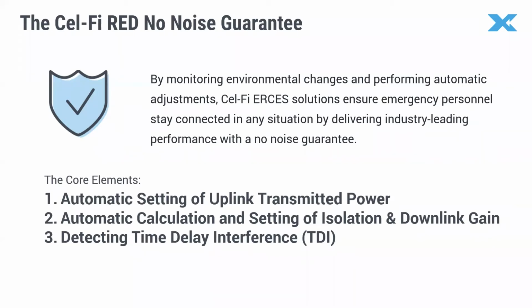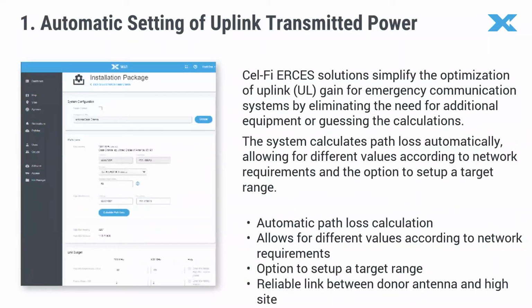Let's review the core elements, starting with the automatic setting of uplink transmit power. One of the most critical steps when commissioning a public safety BDA is setting up the communication link between the BDA and the remote tower. This process usually requires technicians with advanced RF skills and special gear to measure and monitor the signal traveling to the remote tower. It's critical because an error in the calculation can jeopardize the performance of the whole network.